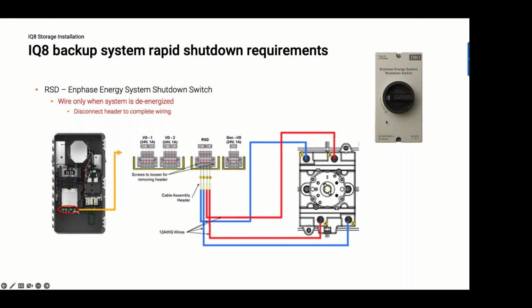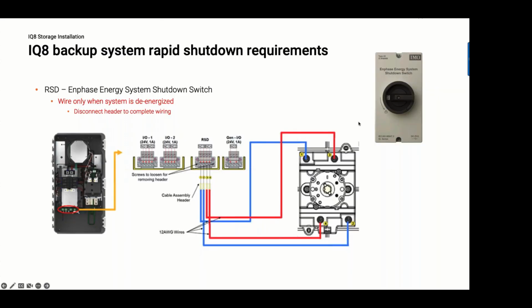What does this switch do? This switch provides all of the rapid shutdown requirements needed to be compliant to rapid shutdown. And so that rapid shutdown switch is a separate switch. It can get located anywhere. So if your system controller is inside, you can wire the system controller, the shutdown switch outside so that firefighters can have a rapid shutdown initiator. That's this switch right there.